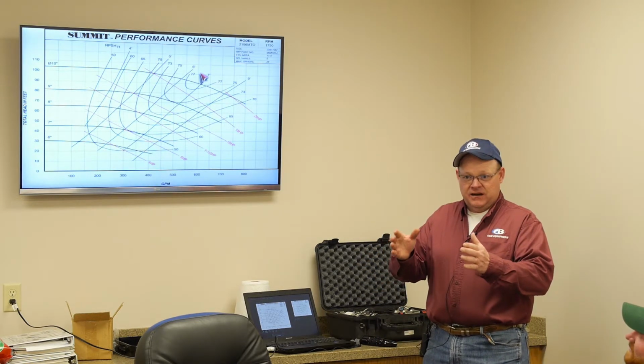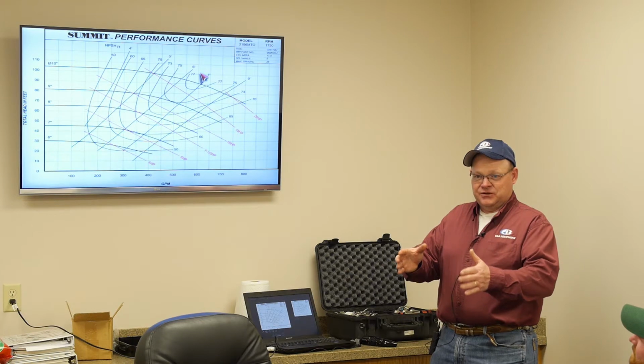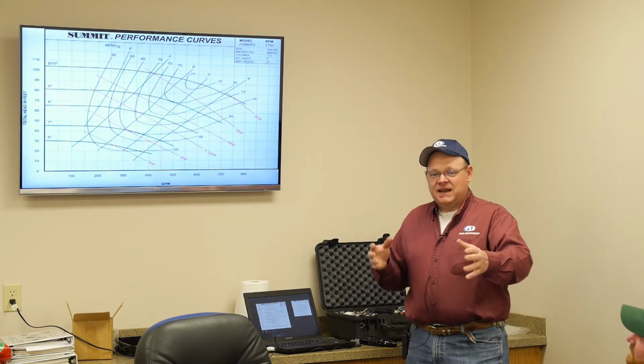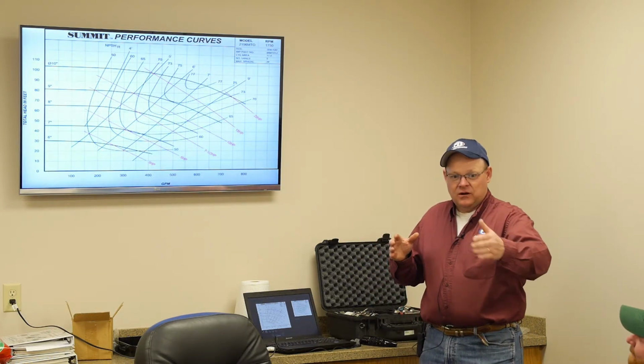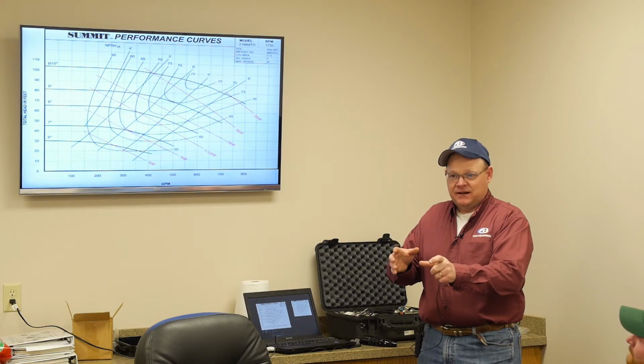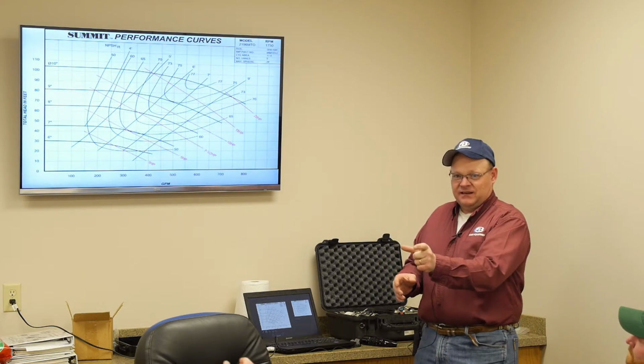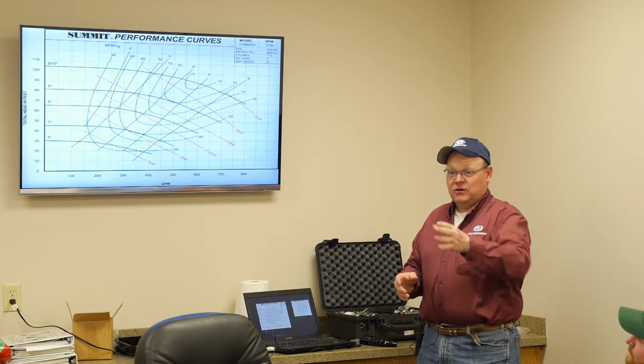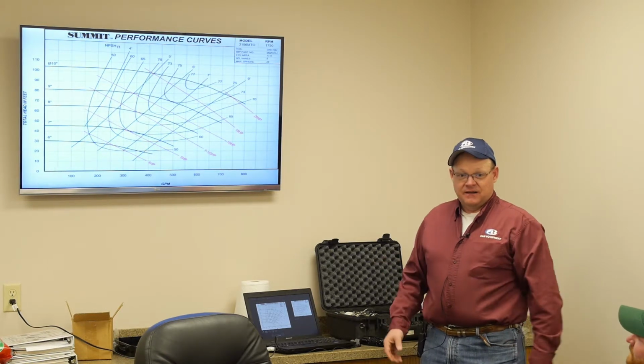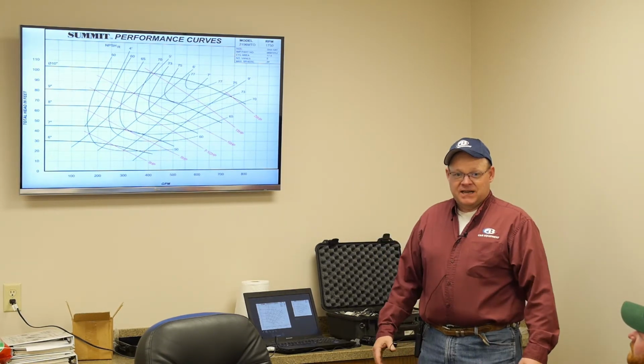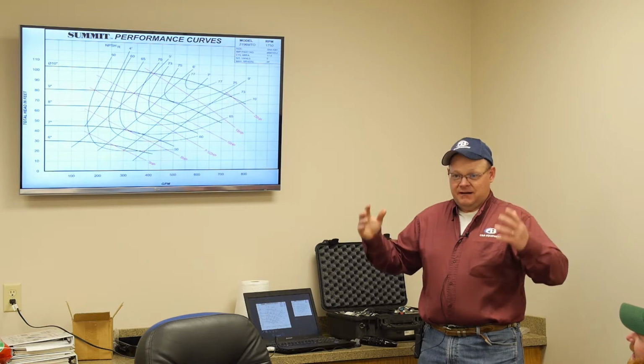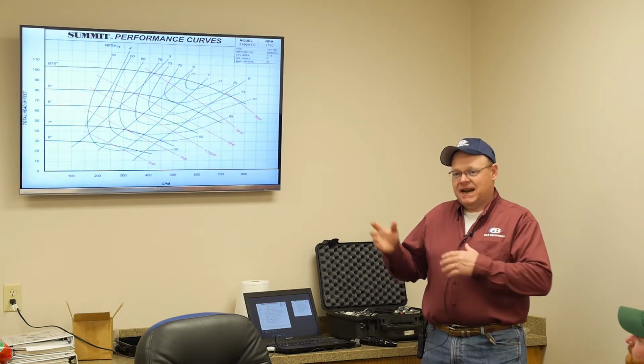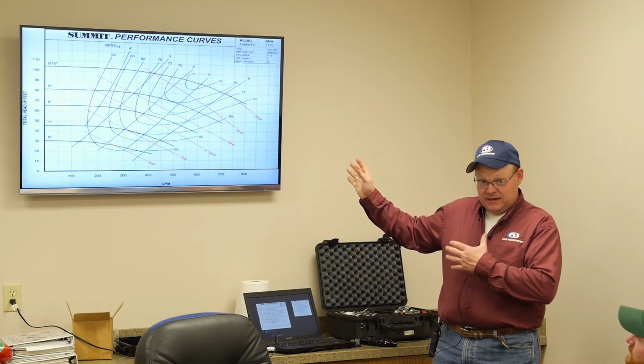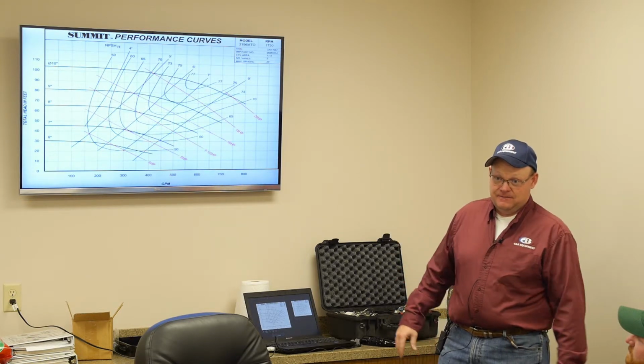You may have inherited a pump that was trimmed to 8-inch, and maybe they didn't write on the ticket or on the pump that it had an 8-inch impeller in it. All you know is on the label it said 3410. You call and order a 10-inch impeller, put it in there, and it trips out every time I turn it on. It just flips the breaker every time. Know and understand that somebody may have trimmed it and not written it down somewhere.